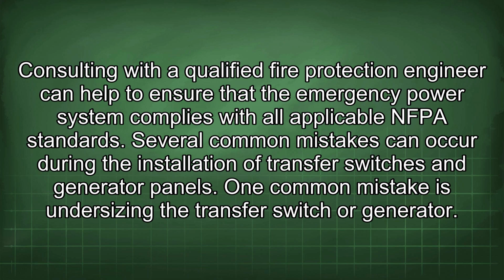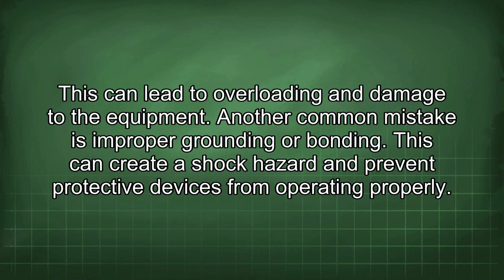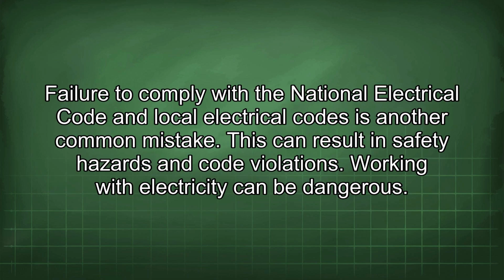Several common mistakes can occur during the installation of transfer switches and generator panels. One common mistake is undersizing the transfer switch or generator. This can lead to overloading and damage to the equipment. Another common mistake is improper grounding or bonding. This can create a shock hazard and prevent protective devices from operating properly. Failure to comply with the National Electrical Code and local electrical codes is another common mistake. This can result in safety hazards and code violations.